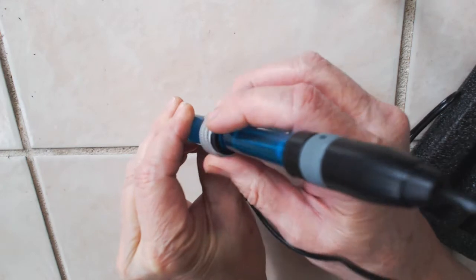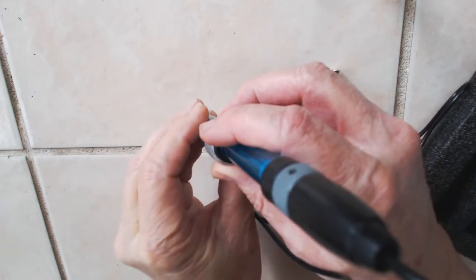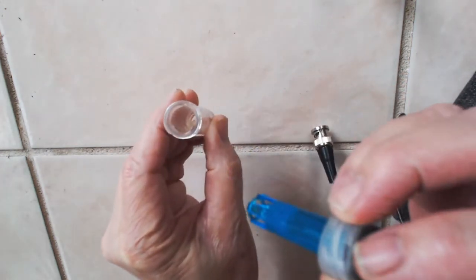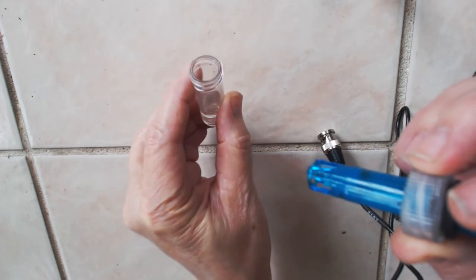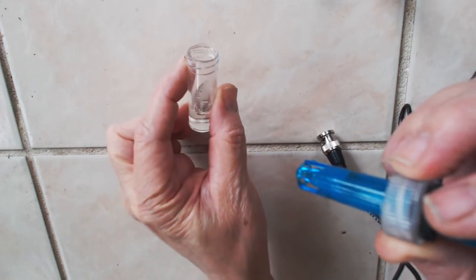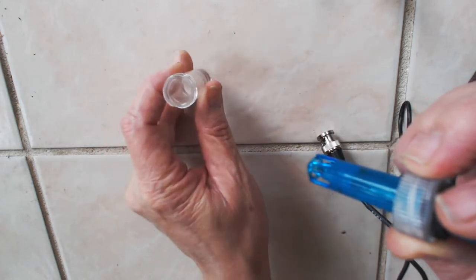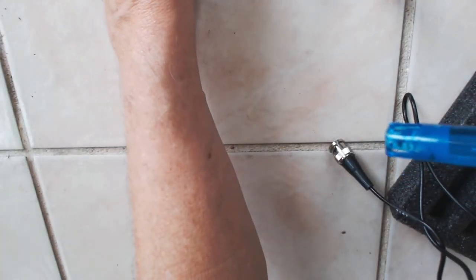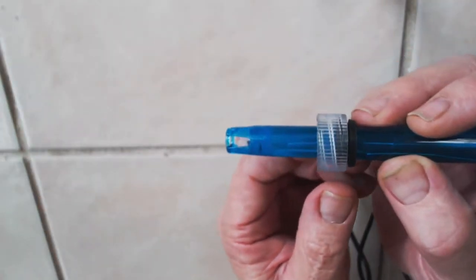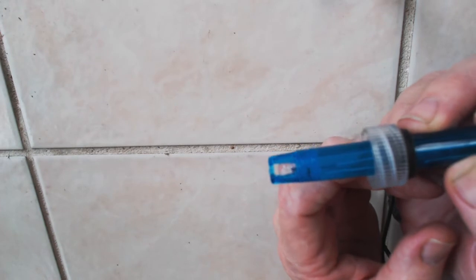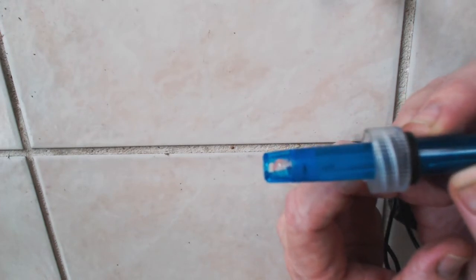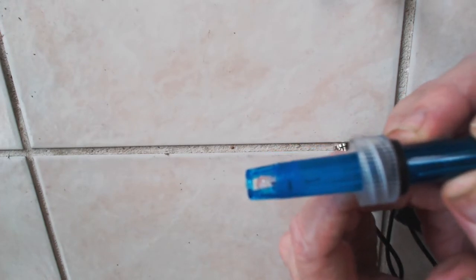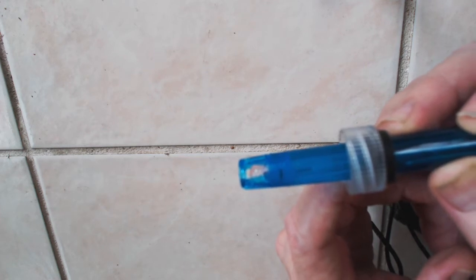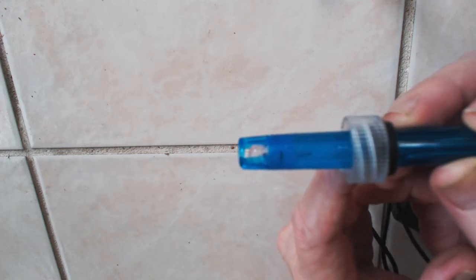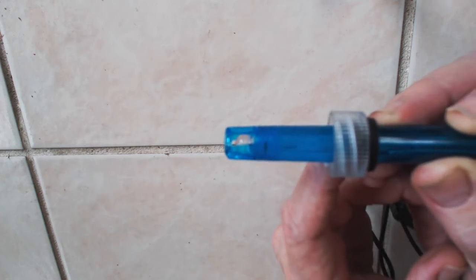You can definitely buy pH meters with the probe built into the meter. I definitely would not recommend this, as you should consider the probe an expendable, replaceable item. They will go bad. The lifetime of a probe is definitely dependent on multiple factors. Number one, how much it's used. Number two, what it's used in. And of course, number three, the quality of the probe to begin with.